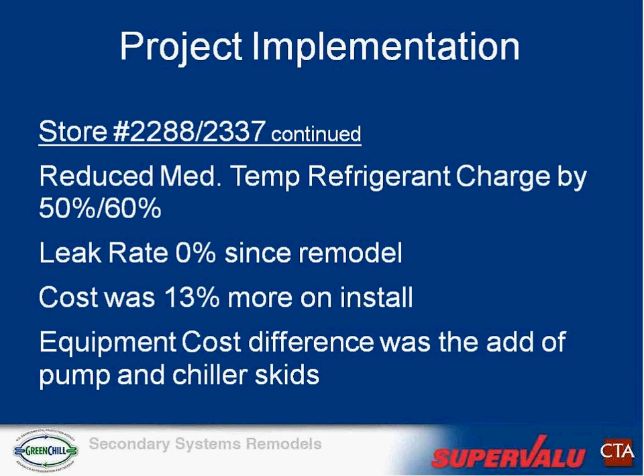So in these 2 stores, we had a reduction of medium temp refrigerant charge by 50% on the 2288 store and 60% on the 2337 store. So pretty significant refrigerant reductions. The leak rates in these stores have been 0 since the remodel. Now I think these stores have basically been online since the later part of last year, so not much time to produce leaks, but it's a good sign.